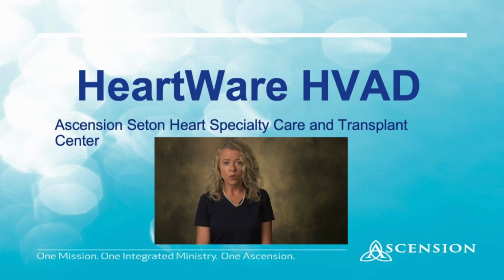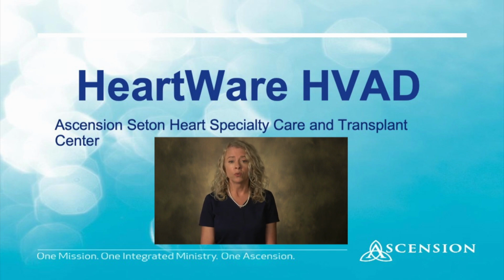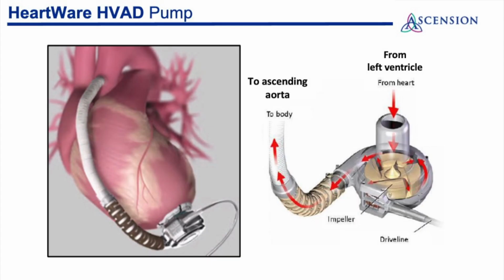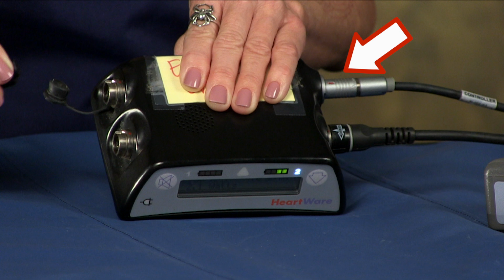We still have quite a few patients in the community with this VAD, and people travel with it, so it's important to review. Remember, this VAD also pulls blood continuously from the left ventricle to the aorta, and the patients may or may not have a pulse, depending on the degree of failure they had when it was implanted. The more support the pump provides, the less pulsatile the patient will be. Connecting the HVAD pump to the controller is a driveline which is inserted here. Like the HeartMate driveline, it's important to check it is secured before transport to prevent tugging and pulling.